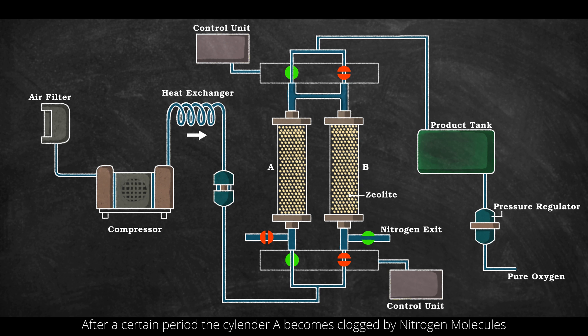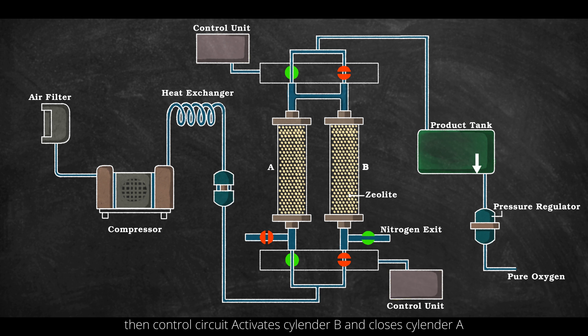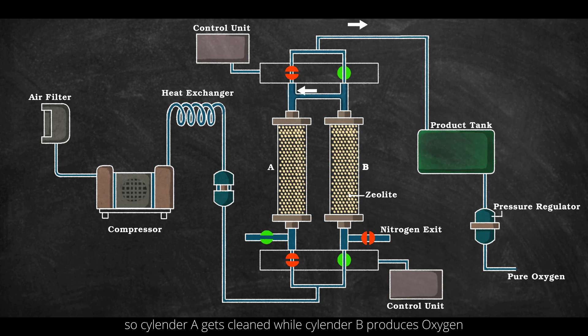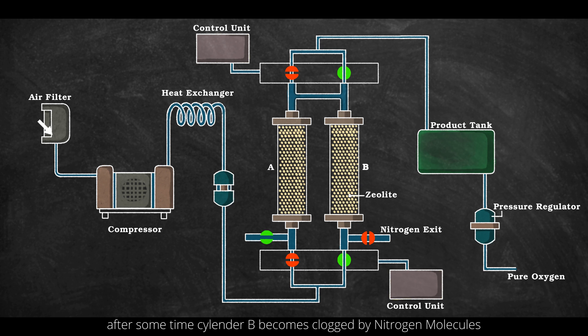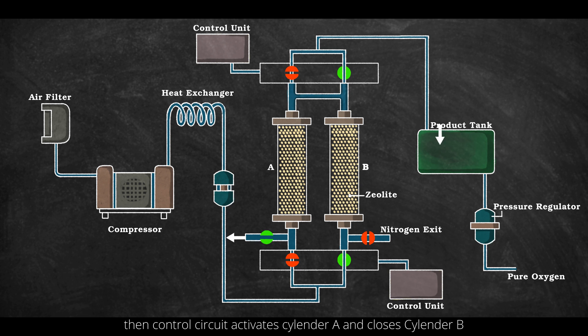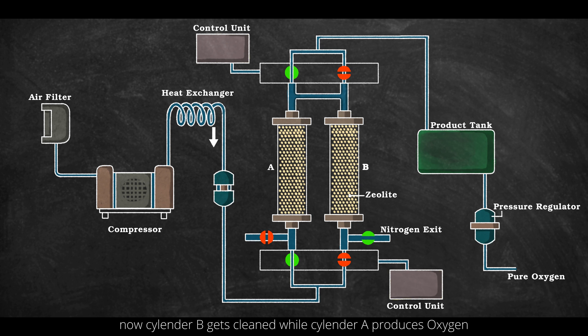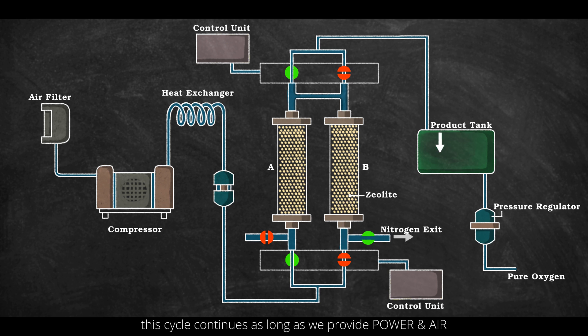After a certain period, Cylinder A becomes clogged by nitrogen molecules. Then the control circuit activates Cylinder B and closes Cylinder A, so Cylinder A gets cleaned while Cylinder B produces oxygen. After some time, Cylinder B becomes clogged by nitrogen molecules, and the control circuit activates Cylinder A and closes Cylinder B. Now Cylinder B gets cleaned while Cylinder A produces oxygen. This cycle continues as long as power and air are provided.